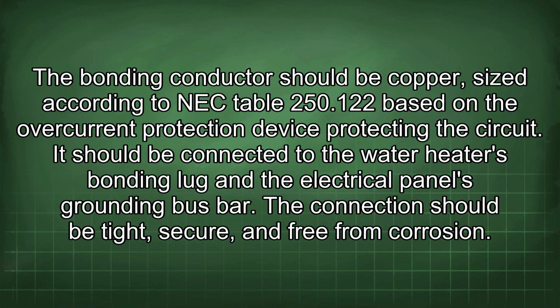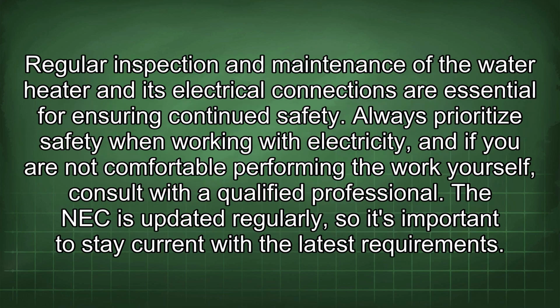safety. The bonding conductor should be copper, sized according to NEC Table 250.122 based on the overcurrent protection device protecting the circuit. It should be connected to the water heater's bonding lug and the electrical panel's grounding bus bar. The connection should be tight, secure, and free from corrosion. Regular inspection and maintenance of the water heater and its electrical connections are essential for ensuring continued safety.